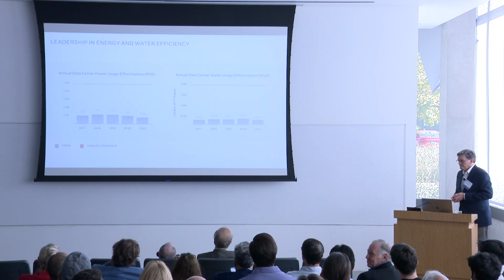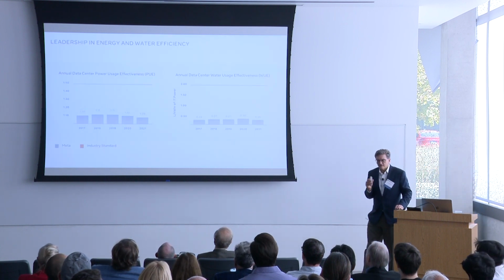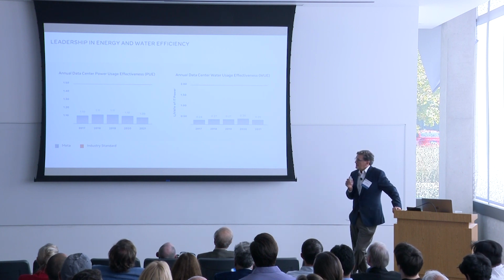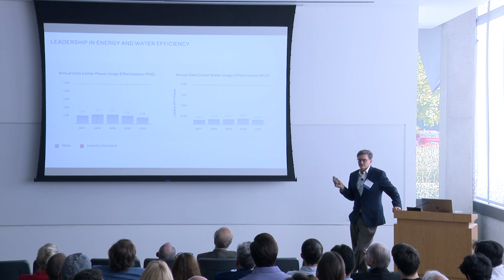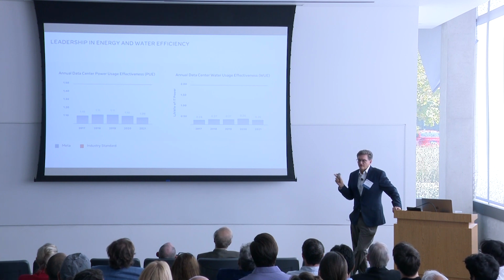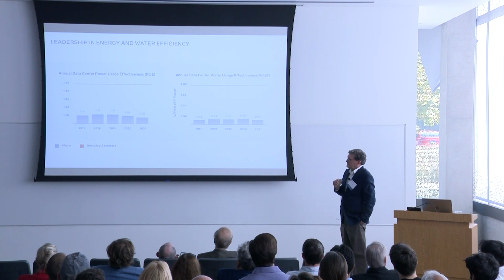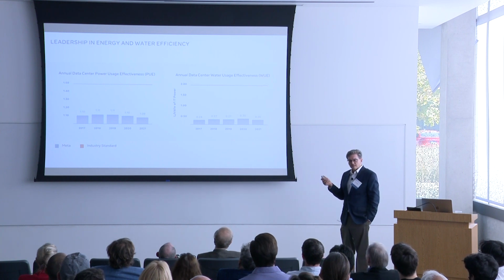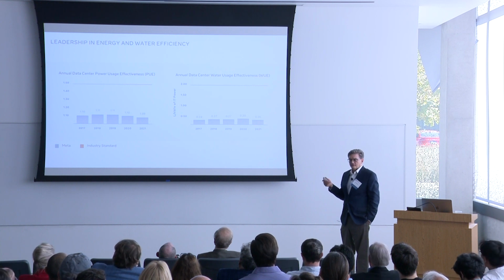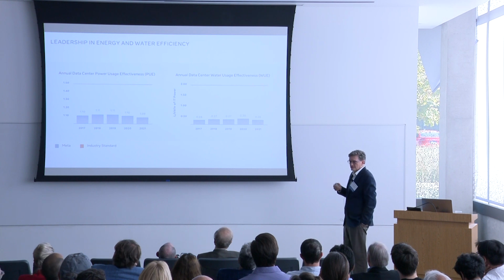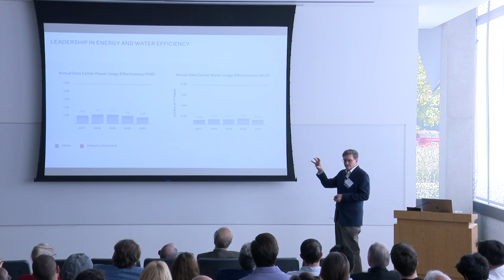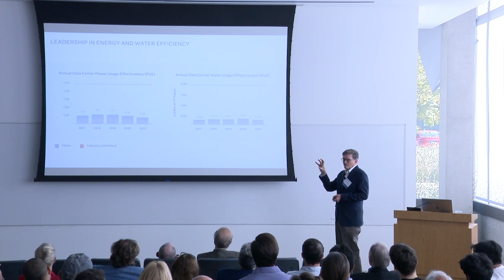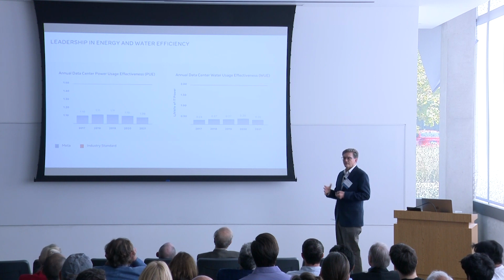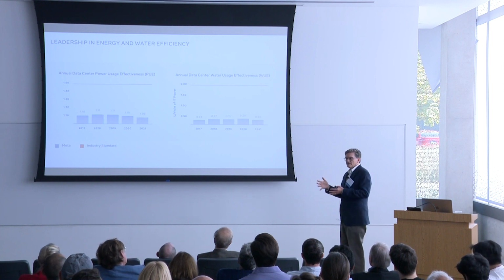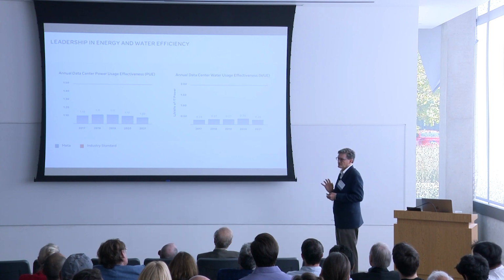So just a little history before I get into the impact of AI on compute and data centers. There are two metrics we use as an industry to make sense of energy and water efficiency. As John referenced, the nexus of energy and water, they're all connected. PUE is the first one, and this is the metric that kind of introduced me to the efficiency world. A colleague and I proposed this in a paper back in 2006, and it measures the total amount of power going into a data center divided by the IT power. So anything above 1 is waste, or essentially the burden of mechanical power and cooling power to make the IT run. You want the number to be as close to 1 as possible.